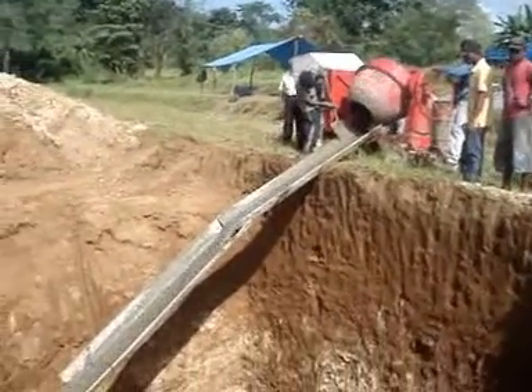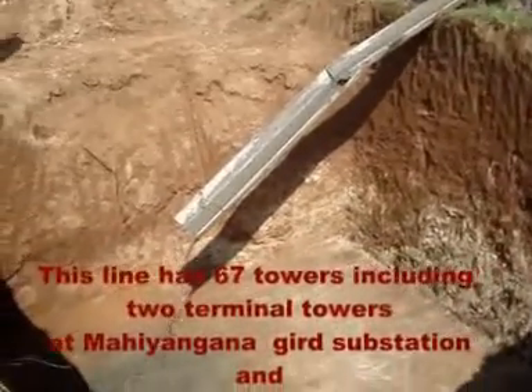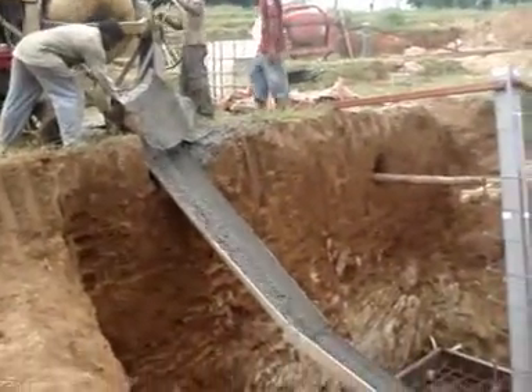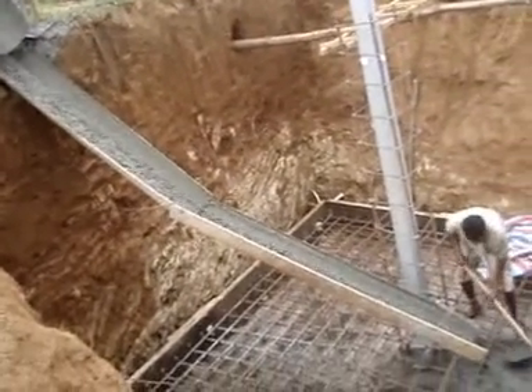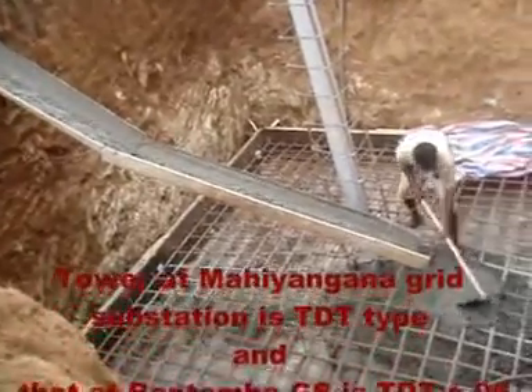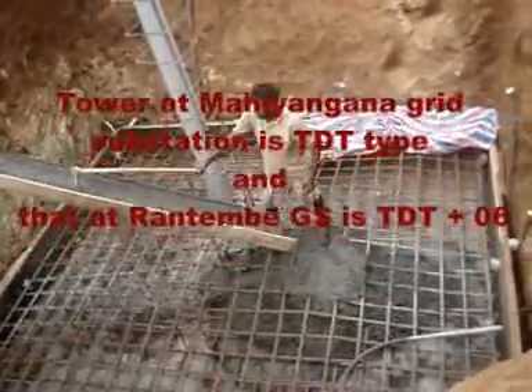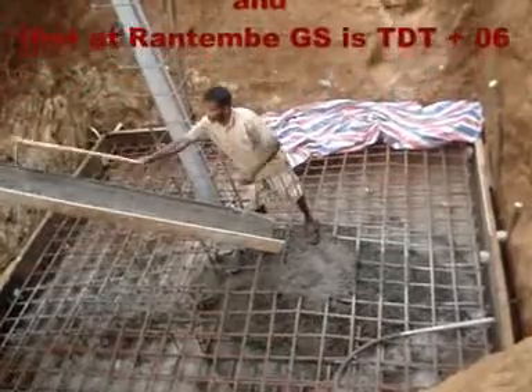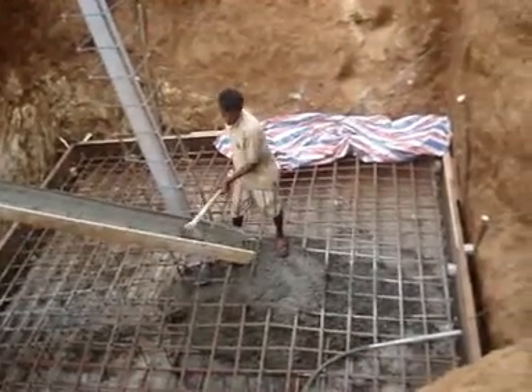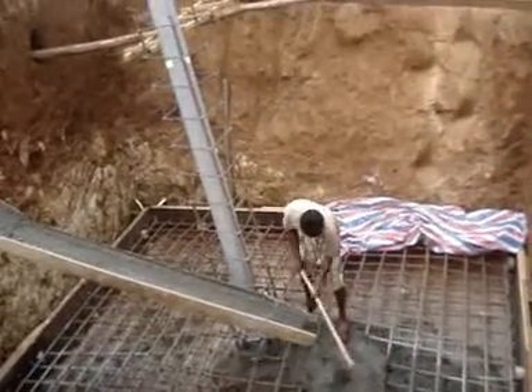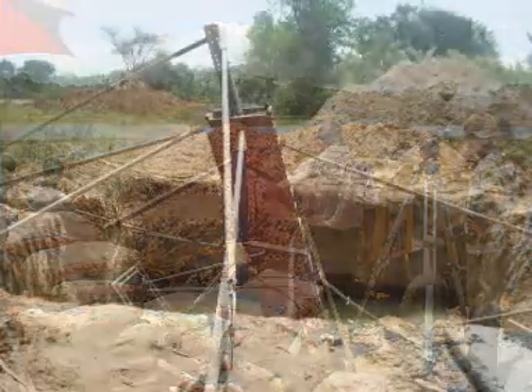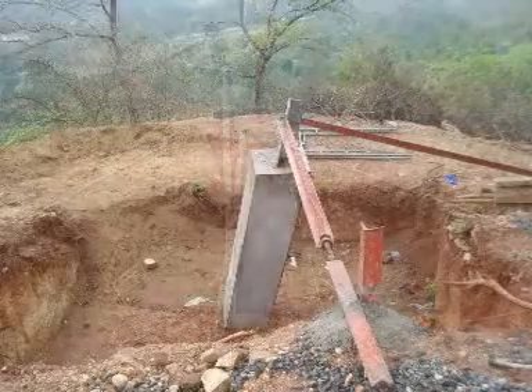This line has 67 towers, including two terminal towers at Mahiyangana GSS station and Rantembe station. The line has 19 angle towers out of those 67 towers. The terminal tower at Mahiyangana GSS station is TDT type, and that at Rantembe GSS is TDT plus 6. TD1, TD3 and TD6 towers are also in the design, in addition to TDL towers. Soil investigation tests were carried out for all the tower locations. Accordingly, foundation types are selected.